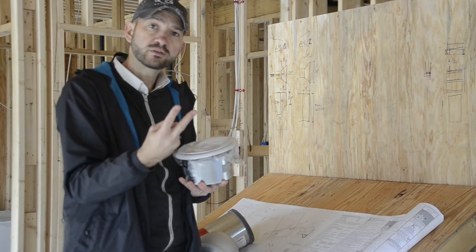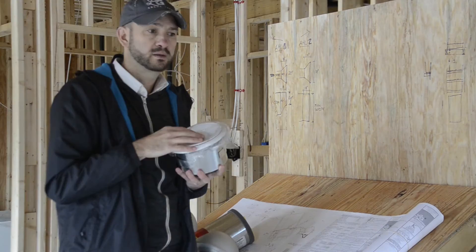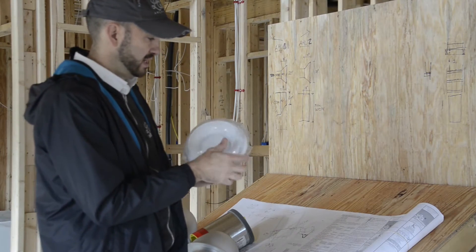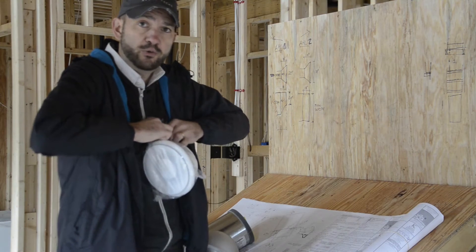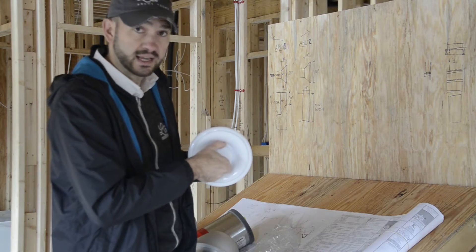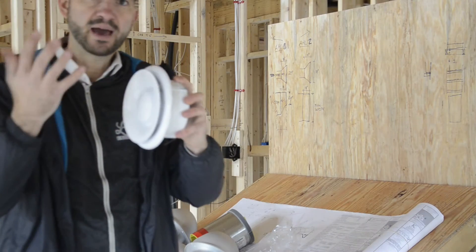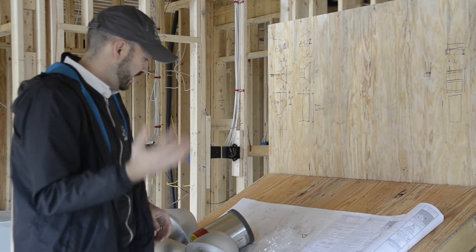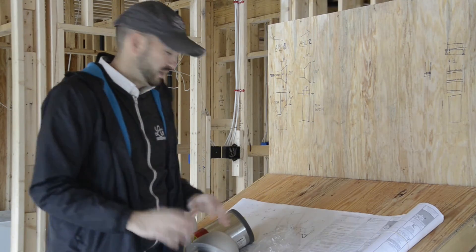So we have two systems — two inline fans, one bringing fresh air in and one exhausting the bad air. The exhaust system is pulling from a central space in the home through this duct. This Fantech grill is adjustable — as you twist it, it opens up — so we can regulate the amount of air here and at the fan. We have a lot of ways to control the flow, and when we test and balance the system we can make adjustments in multiple locations.